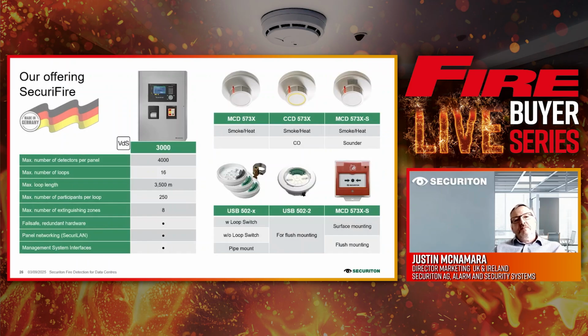I'm then going to switch back to the SecuriFire panel. I'm highlighting here our 3000 range, purely and simply because it's the biggest, the flagship of our range. We can put up to 4,000 detectors on a panel, 16 loops, a loop length of 3.5 kilometers, 250 devices maximum for each loop. Really is a truly powerful, remarkable, dare I say, unique detection and extinguishing panel.